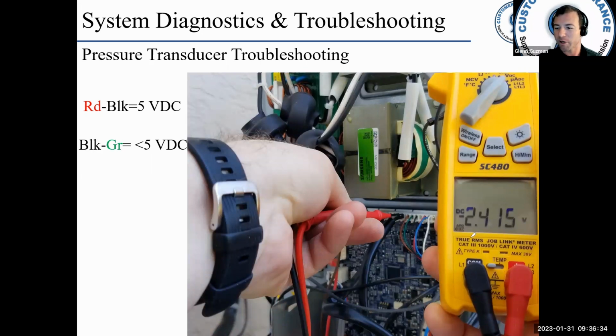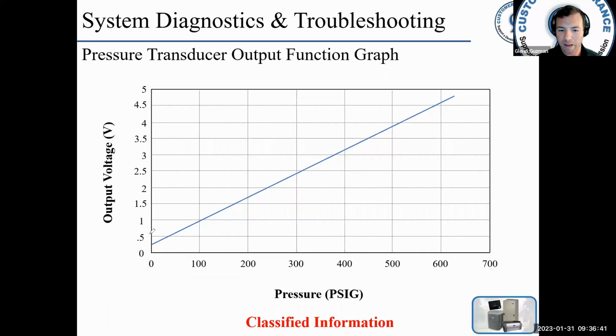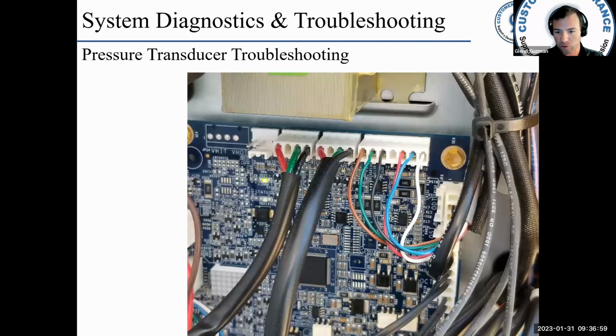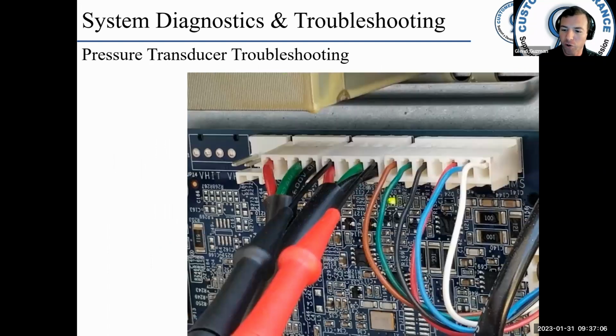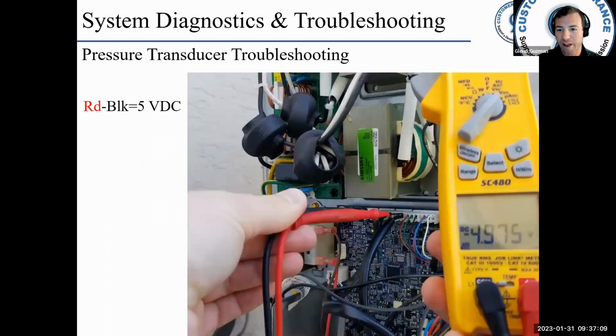In this case, when I took the measurement, it was 2.41. So if I want to know what pressure that is, I can come back here. Here's my 2.41, give or take. So I was probably somewhere in this area, almost 300 psig. Now you can read these voltages with the unit in standby. The unit doesn't have to be actively running for you to read these voltages. In fact, a lot of times I'll have guys go to the user interface and just look at the status screen and see what the unit is doing right now. The unit's not running, but it's still going to be reporting a pressure.